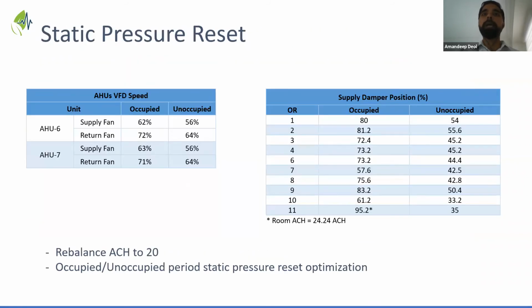One of those opportunities is around static pressure reset. When we analyzed the overall project requirements and the air testing reports, what you can see here is a summarized VFD speed for AHU 6 and 7. In the occupied mode the fans are running at 62 and 63, and in unoccupied, it goes to 56.